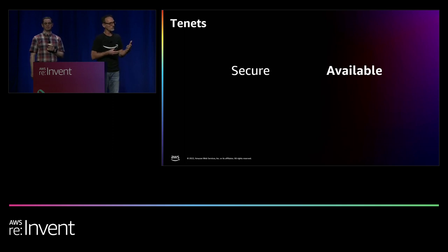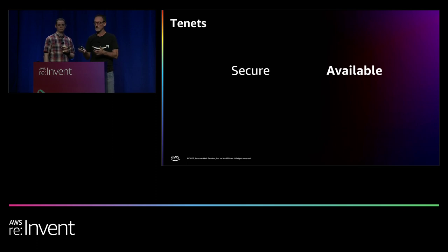The network itself, as we'll discuss quite a bit today, is built of a lot of redundant switches and links. We provision redundant capacity to all layers. We monitor that capacity to ensure that the network always meets our expectations. We put our switches on diverse power feeds. A lot of people do that in colo locations. You may have hosting things in colos yourselves. We also use backup systems. A lot of colos have those as well. We have redundant backup systems. So we'll put our network switches on diverse power feeds with diverse backup systems so that we can take a hit almost anywhere and not bring down the whole network or a whole data center.